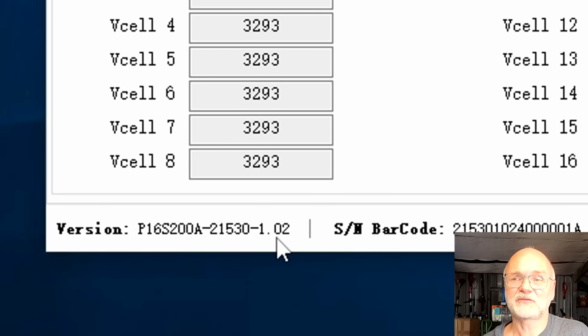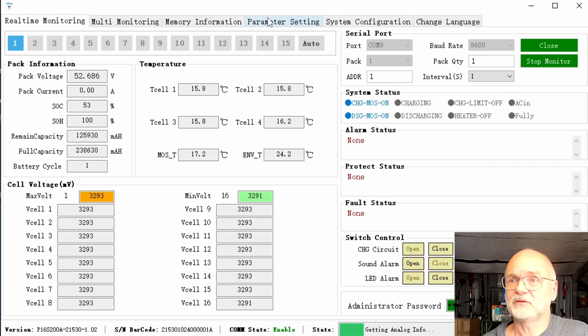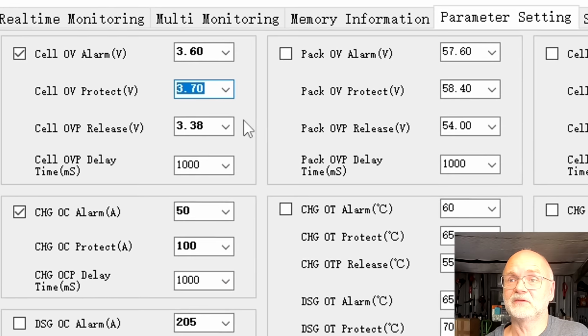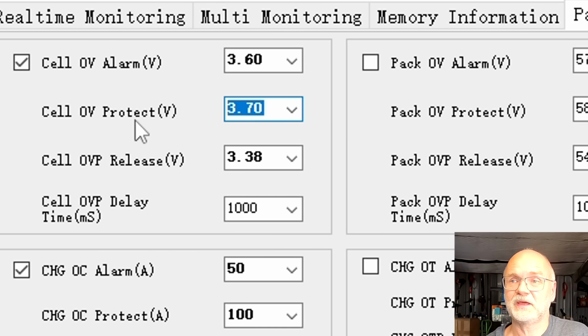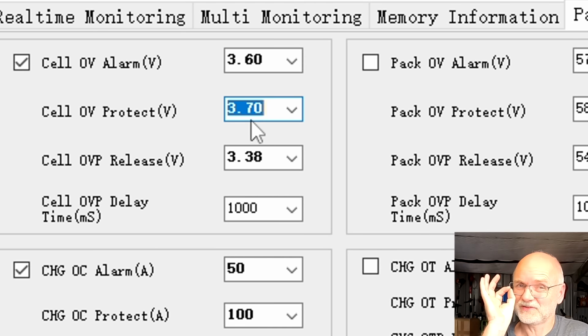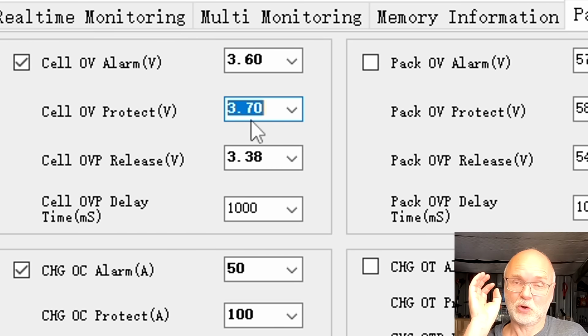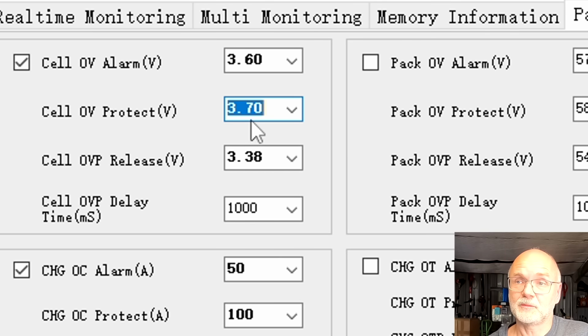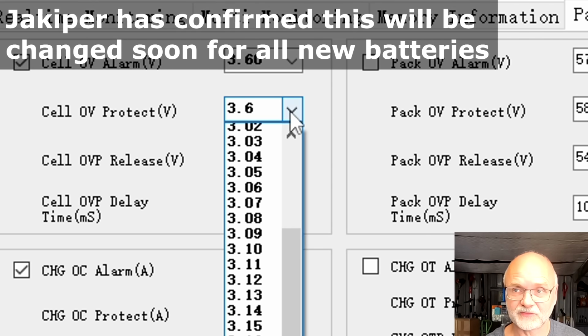It looks like we have a newer software version here as well, 1.02, while in the smaller Jaki battery it is 1.00. But this could also be related to the larger 200 amp BMS here, so there might be a different firmware version anyway. All the other parameters, all the settings are pretty much the same. There's no new functionality with this BMS. So what I found here as well is the cell over voltage protection sits on 3.7 volts, which is a tiny bit too high for these cells. They should only be charged to 3.65. So make sure you change this one to 3.65.